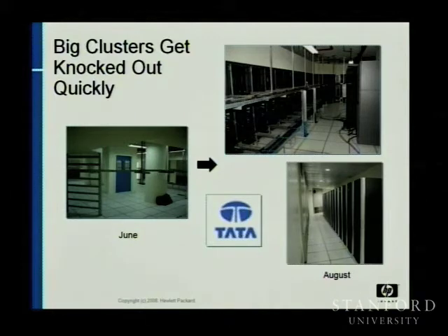We were talking about data center design. These things peak out at more than 32 kilowatts a rack when they're running HPC applications. And so they've done an interesting thing. Servers are traditionally designed with front to back cooling. Cold air comes in the front, hot air comes out the back. What they did to avoid mixing is they put in a drop ceiling right in the middle of the racks. And so you have a ring, concentric rings, of hot and cold. So pretty clever.